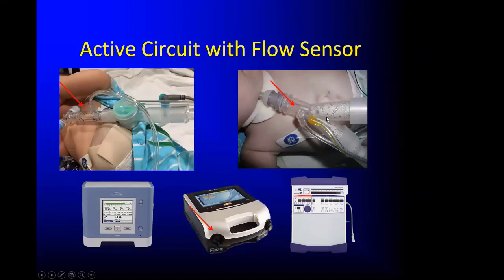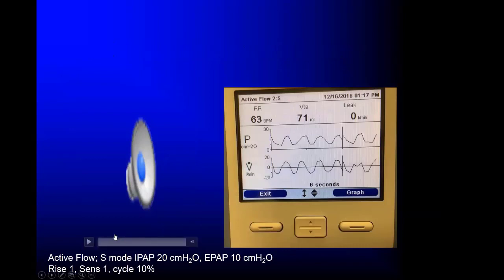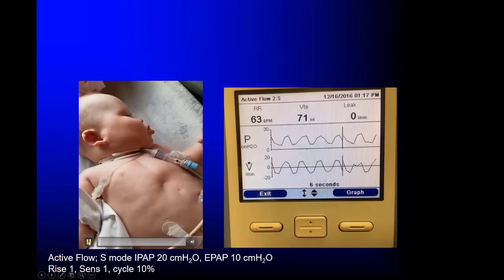So when we use an active flow circuit, you have to know where your flow sensor is, but I will tell you all of these machines are quite sensitive, even when the flow sensor is not right up against the airway opening. So as I mentioned, there's the flow sensor for the LTV, there's the flow sensor for the Trilogy. The flow sensor for the Astral is back at the machine, but it's quite sensitive as well. So I want to show you why you might not want to use an active flow circuit when you've got a big leak.